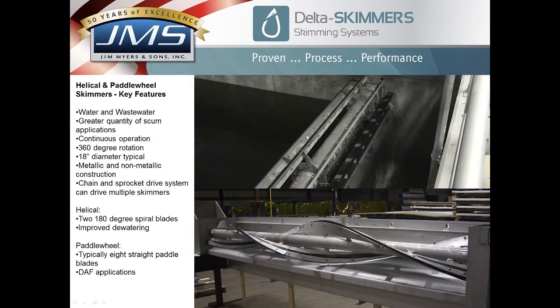So these paddles kind of bite into the scum and pull the scum up the beach, and it pulls the surface scum towards the paddle each time it does that. So that's why the paddle wheel skimmer versus the helical. The paddle wheel skimmer, once it grabs that scum, bites onto that beach, and it's pulling the water up. Anything it's grabbed, it's pulling up the beach and over the trough. A helical skimmer, down at the bottom here, has the advantage that it grabs the scum, but as it's pulling it up the beach, the free water has the ability to flow back down the beach and back into the basin, just because of the helical configuration of the paddles.